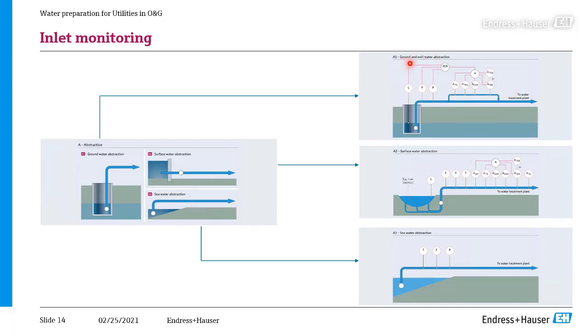So for ground or well water abstraction, you want to measure the water level here. Then the water is pumped this way. So you need to measure flow to know about the amount of water and the volume that you pump here, and pressure. And then here you have already the first quality parameters. You measure turbidity, nitrate, because we are talking about groundwater or well water, so nitrate can be there, conductivity, and also TOC to give an idea about organic pollution. And from there it goes to the water treatment plant or to make up water.